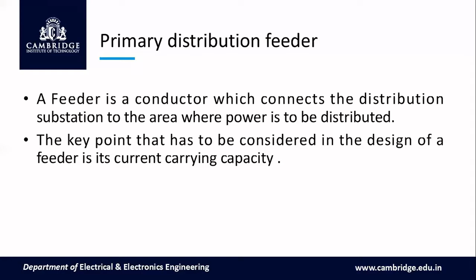Next is the distributor and the service mains. In a distributor, generally tappings are taken for supply to the consumers. The important feature to consider in designing a distributor is its voltage drop along its length. So in the earlier case, we need to consider the current carrying capacity, whereas in a distributor, we need to note down the voltage drop.